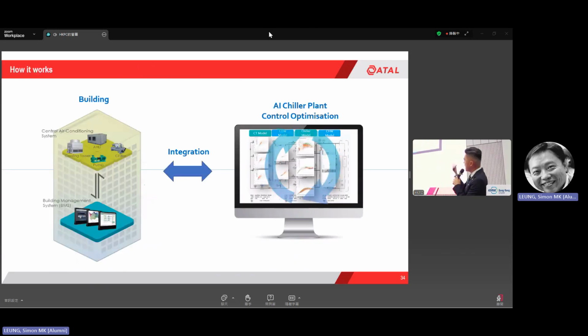With that, every piece of equipment, chillers, pumps, and cooling towers, has a specific machine learning model. With this model, just like we can ask the AI, if we control like this, what is the energy use? With this ability, it can automatically search for the optimum control setting for energy efficiency. And that setting can be passed back to the BMS by BACnet to control the plant. That is how we operate, and this has been implemented at our ATAL cloud.